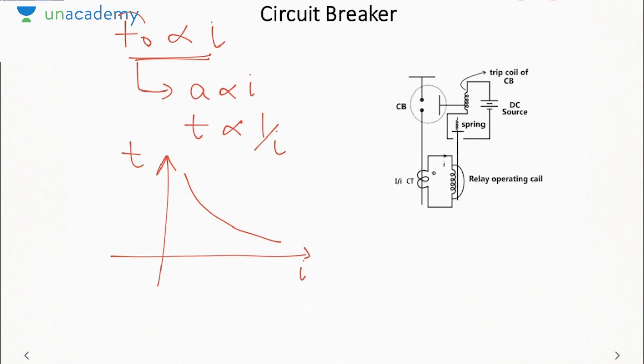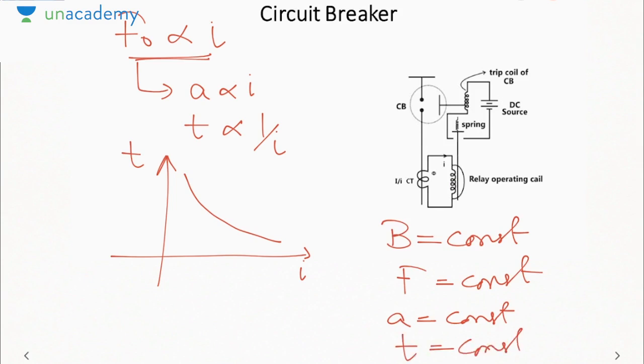Now suppose in the event of a high current, the instrument transformer saturates. If it saturates, the magnetic field that it produces will become constant, due to which force will become constant, due to which acceleration will become constant, and time will also become constant. Now if time becomes constant, it will not be able to operate faster at a higher value of current. And if it does not operate fast at a high current, then what will happen? The high current will persist for a longer duration and it will be able to damage the system. Hence we want that the higher the current, the lesser the time of operation. So the transformer must never saturate.